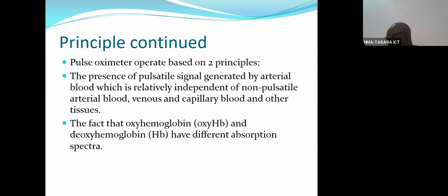Currently available pulse oximeters use two light emitting diodes that emit red light at 660 nanometer and infrared light at 940 nanometer wavelength. In the red region, deoxyhemoglobin absorbs more light than oxyhemoglobin, while it is reversed in the infrared region. At 800 nanometer, the isosbestic point, absorption is equal.